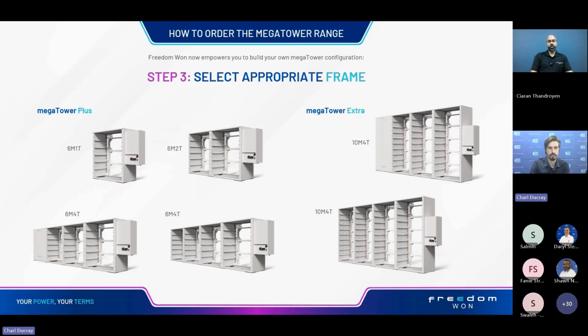Before we move on, the modularity allows these packs to be expanded over time - you can see your blanking panel. So if you want, you can start off with a full 6M4T frame but only populate 1 tower, and over time, as your site requirements or budget increases, you can populate the rest. We've seen clients do this if they need capacity over a 20-year lifespan, starting off populating the first tower and over time populating more towers as required.